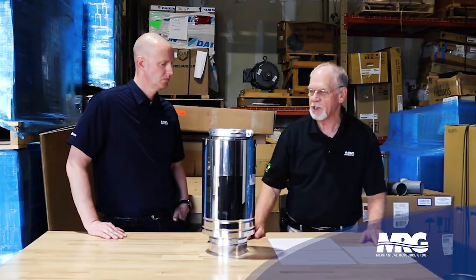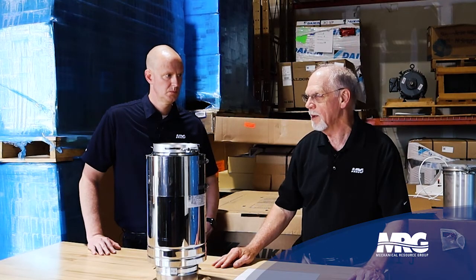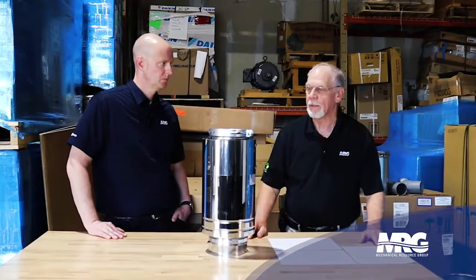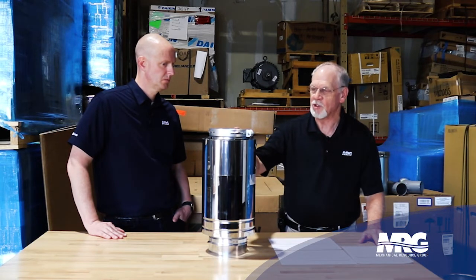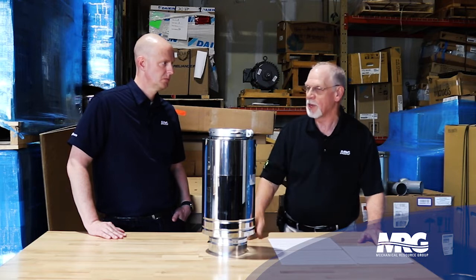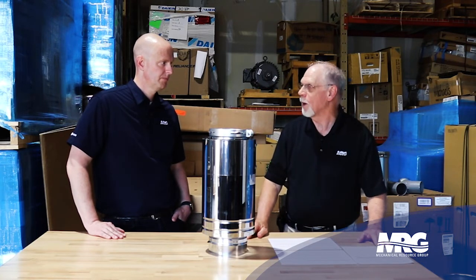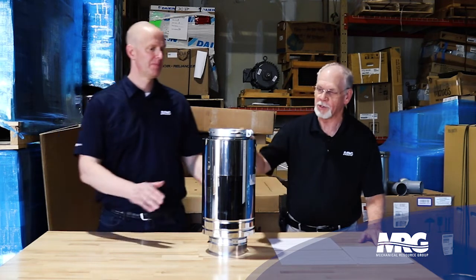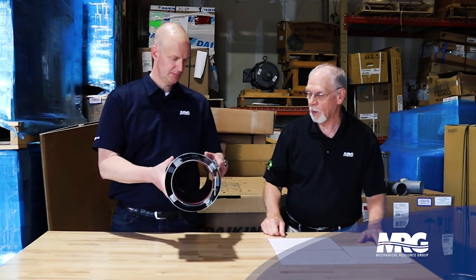So the installation needs to be critical on being able to have fall for the vent to allow the water to get back to an outfall to drain. The only problem I've seen with this is if the joints aren't lubricated when they install those, that rubber seal can roll, and now you don't have a solid joint and you get a leak. You roll it out of the groove seat. It has a groove on the inside, and it will roll it out.